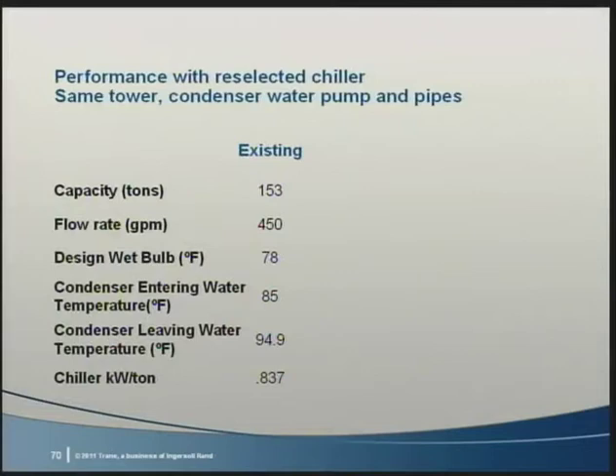There are alternatives. Here's an example with an existing helical rotary chiller of just over 150 tons with 450 GPM of condenser flow. The tower was originally selected at 78-degree wet bulb and 85-degree entering condenser water temperature, which results in just under 95 going back to the tower. It met the ASHRAE 90.1 requirements when it was selected 20 years ago.